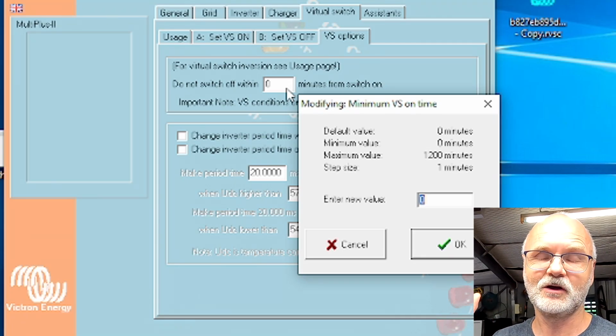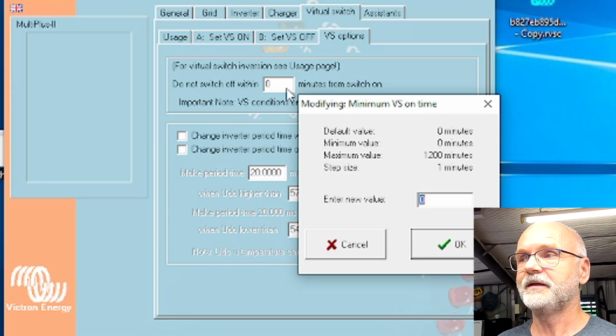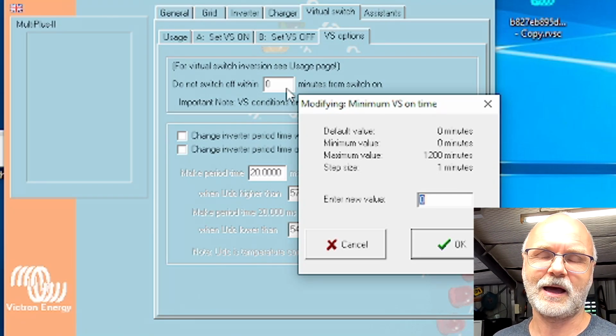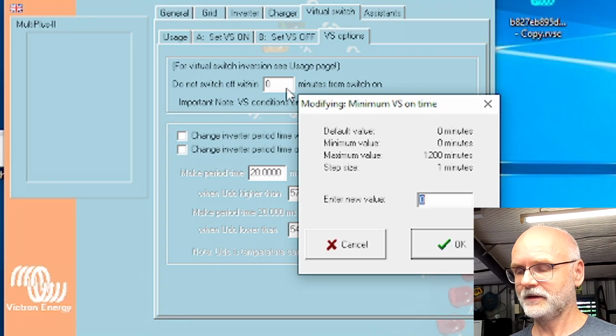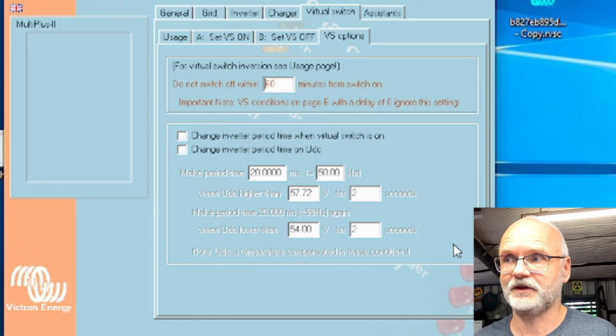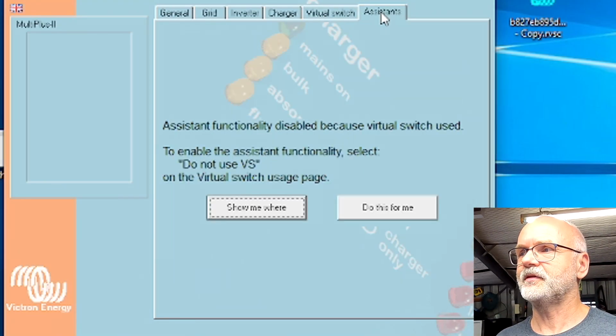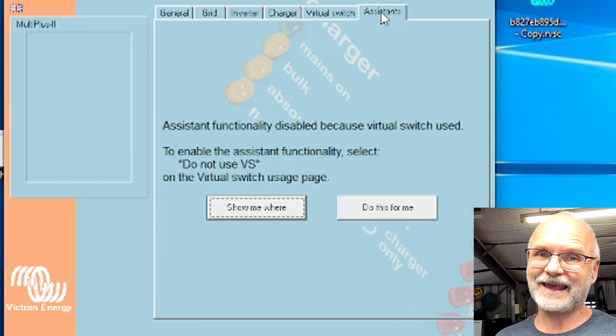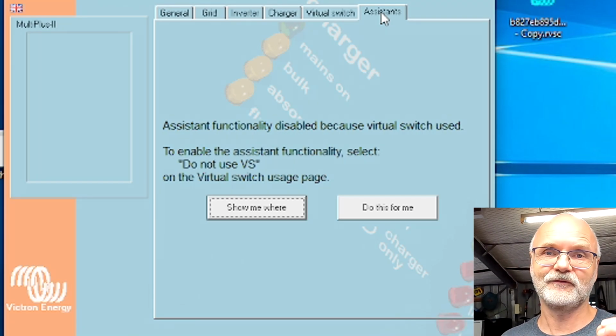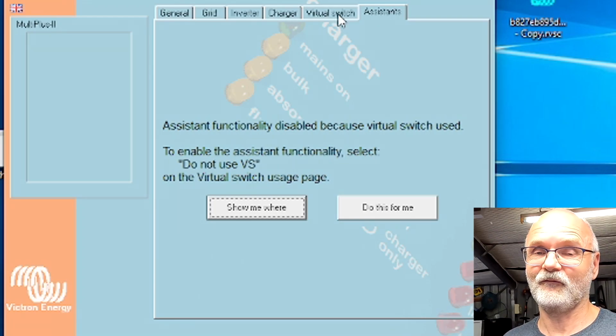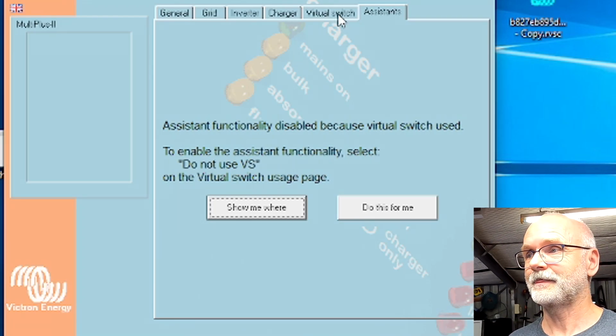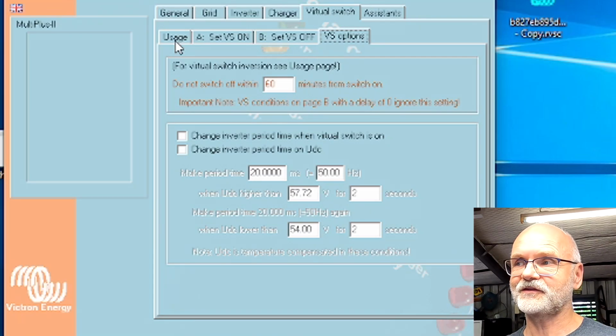If you get a peak overload situation of the inverter, you want to keep it running for a couple of minutes to warm up and actually supply some power to your system. So we could set this one to 60 minutes here. And here in the last main tab, there are the assistants, which we cannot use because we are using the virtual switch already. So the assistants in the Multiplus are a very powerful feature. And I actually want to use the assistants rather than the virtual switch.